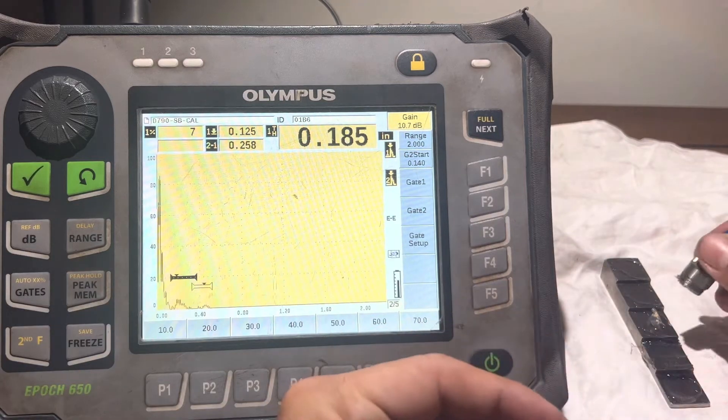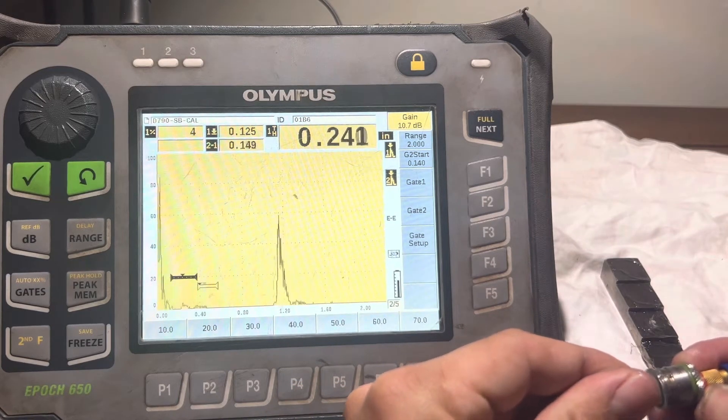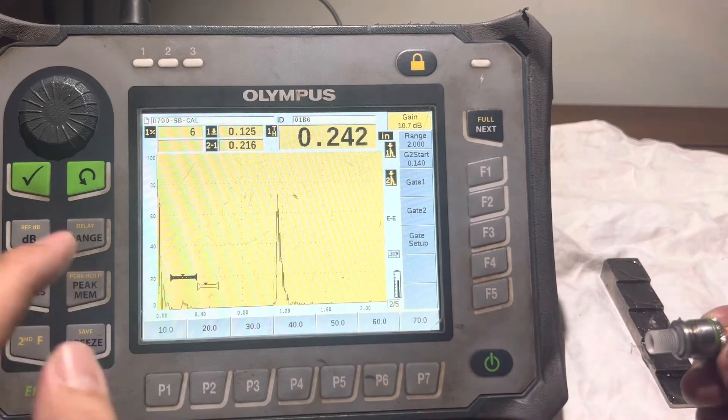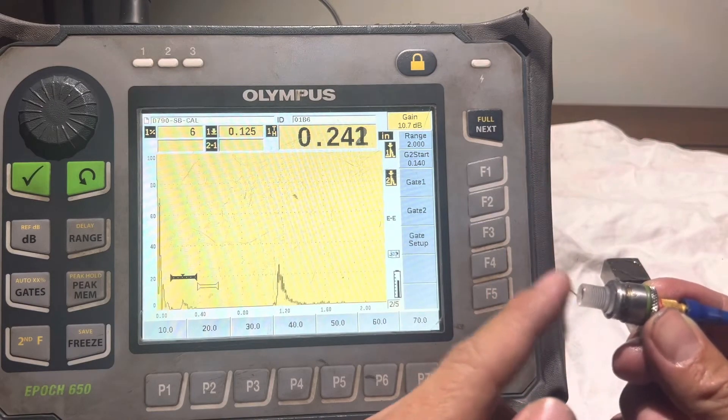What you want to do is you want to get a little bit of couplant and actually place it into the standoff like that. And you'll see the peak of the standoff, that's that right there, you see it moves and that's the standoff.